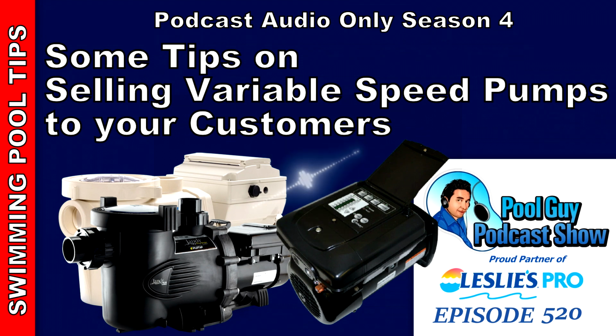And that's up to you as the pool service provider to educate the customer that, look, you're going to save a lot of electricity to begin with, and the pool does need a higher speed mode for cleanliness and for circulation. So program in that mode. I'll probably do a separate podcast on the programming speeds that I like and how long I like to run them in pools. But needless to say, they do need to run the pool on a higher speed, not 3450 RPMs, but maybe 2600 or 2400 RPMs for a certain period of time to get the water really circulating and to clean the surface of the pool.